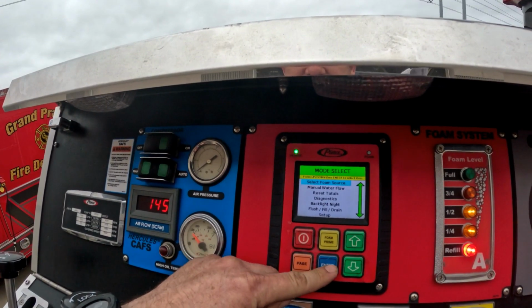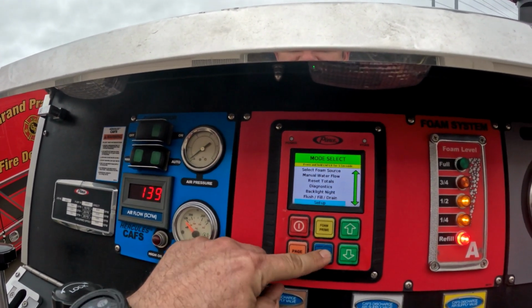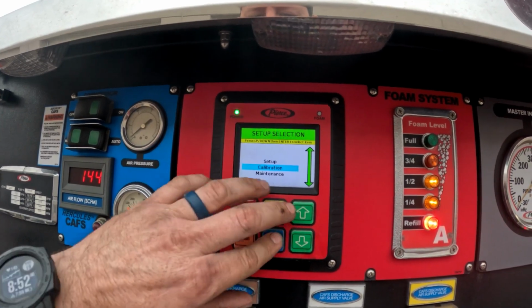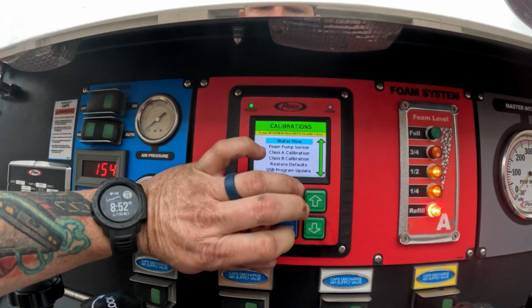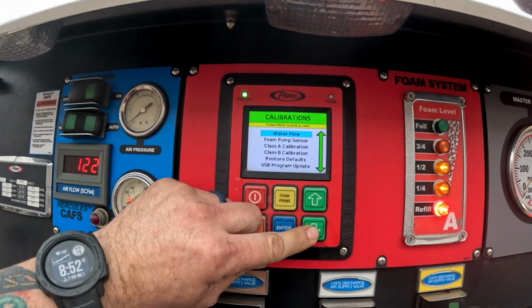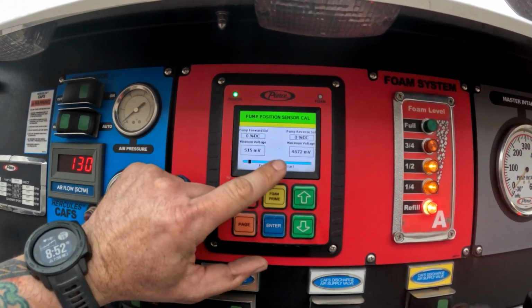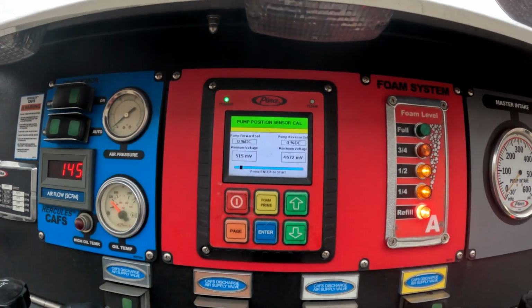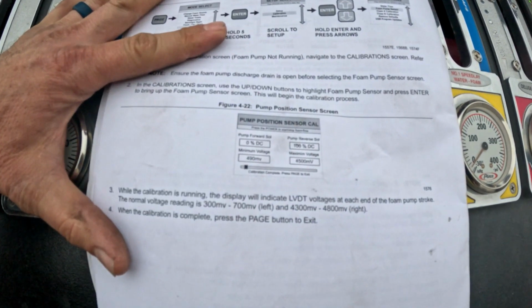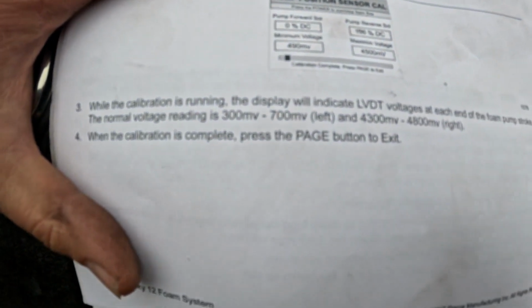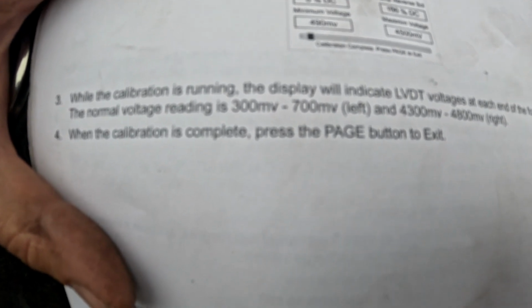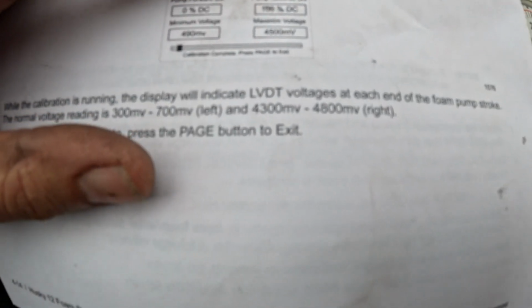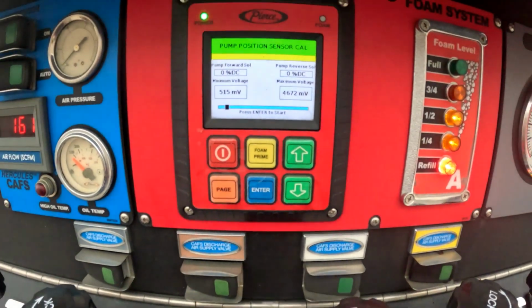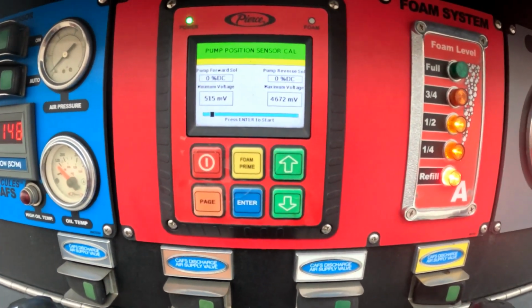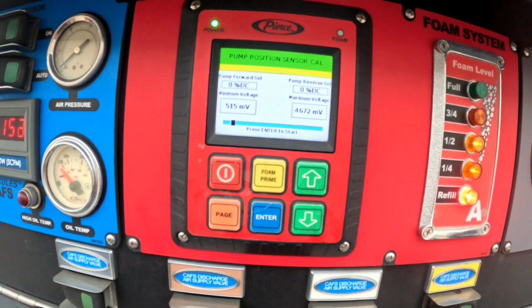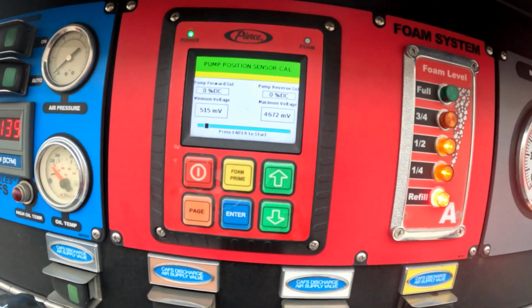So we'll go to page, go to setup, hold for 5 seconds, then go into calibration. You hold enter and up and down. And we're gonna go into foam pump sensor. And right now my voltages are in good range. So if you go to the manual here for Pierce manual, it will show you your left side reading. Normal reading is between 300 millivolts to 700 on the left side, and 4300 and 4800 on the right. And we are at 515 on the left, 4672 on the right. So that falls in between the good acceptable range.